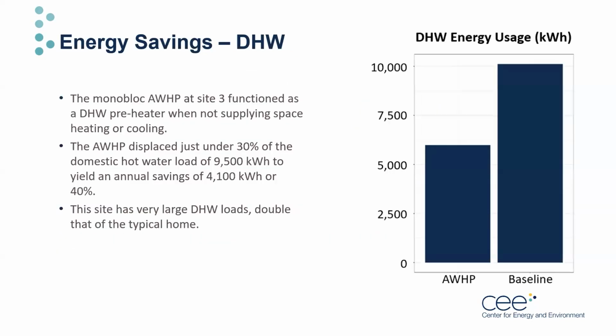In terms of domestic hot water savings, that one site that we did have domestic hot water service at saw huge domestic hot water energy savings. The hot water load was reduced by about 30% to yield an annual savings of more than 40% because the load was more efficiently met by the air-to-water heat pump than by the existing electric resistance hot water heater.